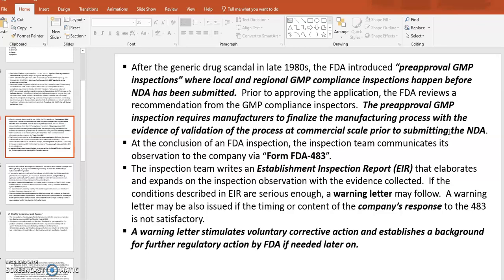At the end of an FDA inspection visit, the inspection results are communicated through FDA Form 483. The inspection team can also write an Establishment Inspection Report (EIR) that elaborates on the inspection observations with evidence collected. If the conditions described in the EIR are serious enough, a warning letter will be issued — especially if the company's response to Form 483 is not satisfactory.